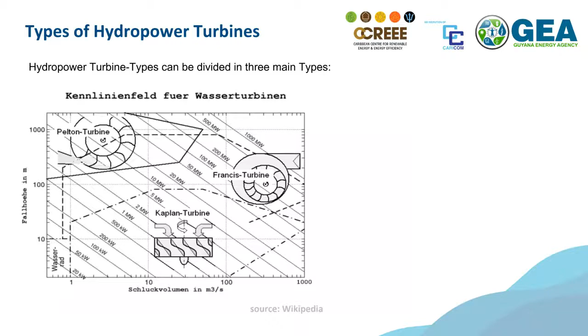I will show you the three main ones. The Pelton turbine is for high head, invented in 1879, so pretty old technology. It's easy to understand on the pictures: you have the branch pipe or pressure pipe with very high pressure, coming to the nozzle, going directly onto the buckets. The stream hits the buckets and spins very fast - a very high speed rotating runner compared to other turbines. Everything is in a casing, closed here, with a high speed runner, and in this example a belt goes to a gearbox to reduce the speed for the generator.